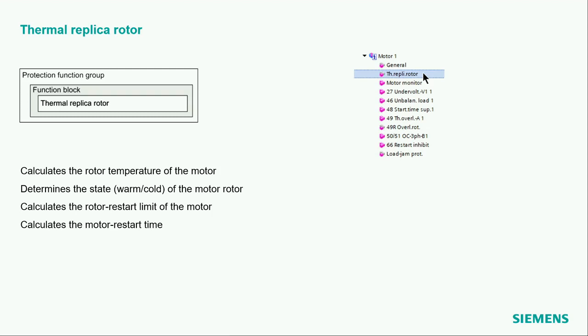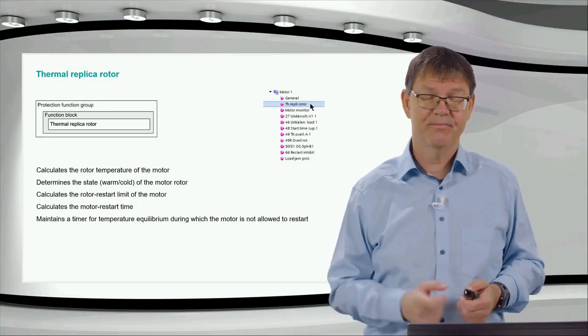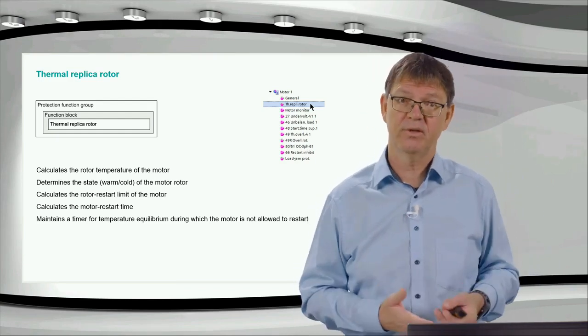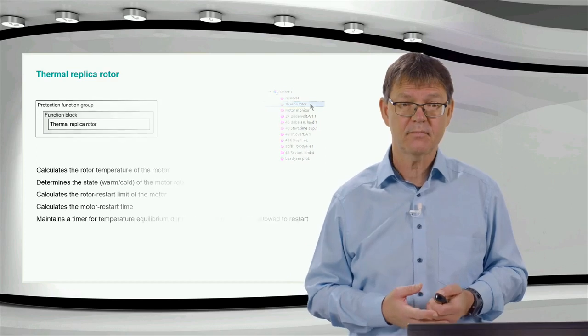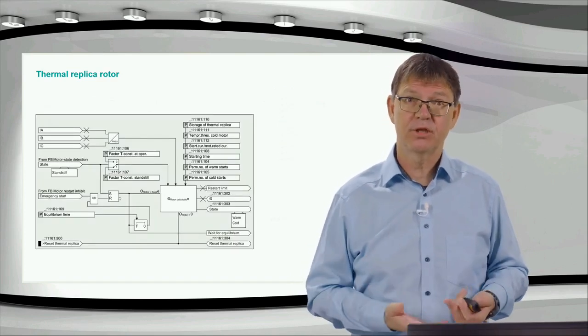It also calculates the motor restart time. That means if I'm above this temperature, how long does it take until I come back to the temperature level where the restart is allowed again? Okay, and we have one more function. This is the so-called equilibrium time. This timer is also handled in this thermal replica rotor. Good, so that's a little bit the logic.